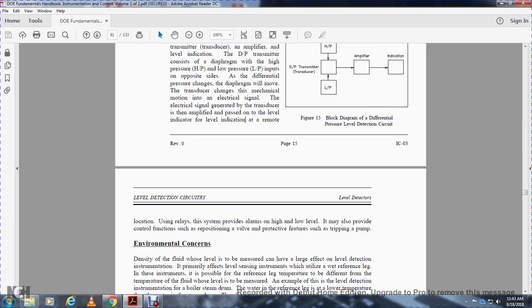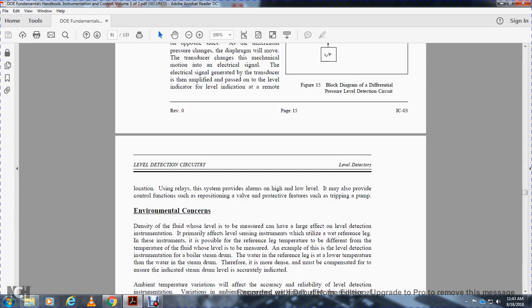Using relays, this system provides alarms on high and low level, and also provides control functions for positioning valves and the protective feature for tripping a pump.